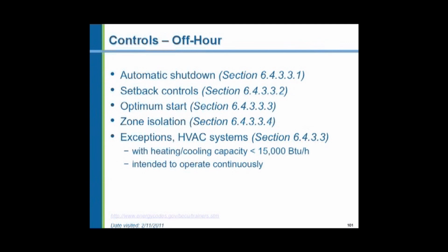They want the system to shut down automatically or to set the temperature back. The optimum start, as we talked about, is a learning algorithm in the thermostat that actually over time sees how the building responds, how long it takes to heat up and cool down. And we have to isolate zones from one another with different zone controls. And again, there are some exceptions, notably heating and air conditioning systems less than 15,000 BTUs, about 1.25 tons.